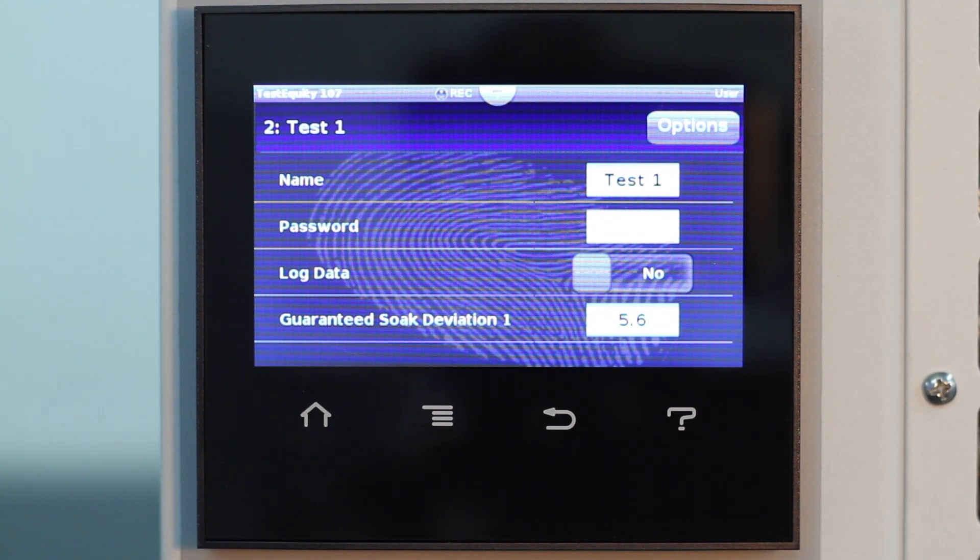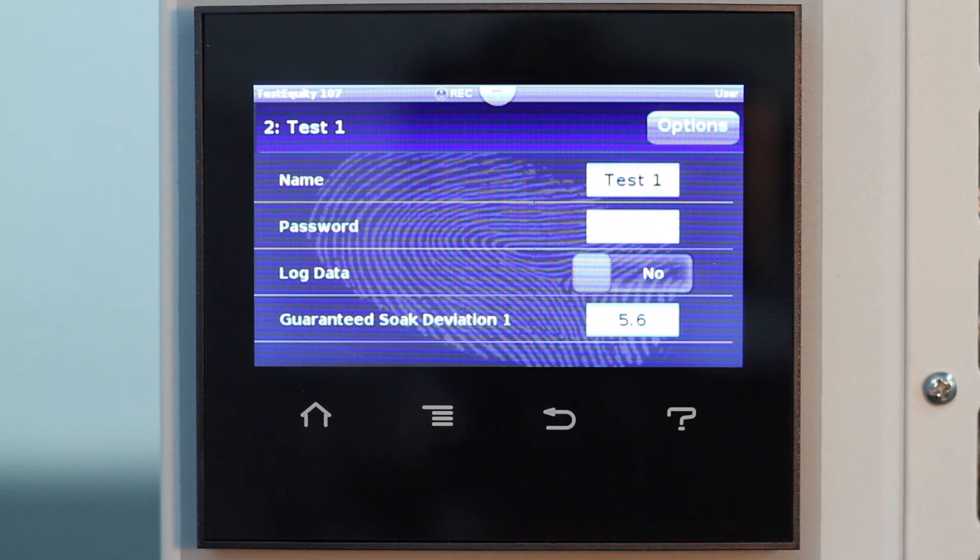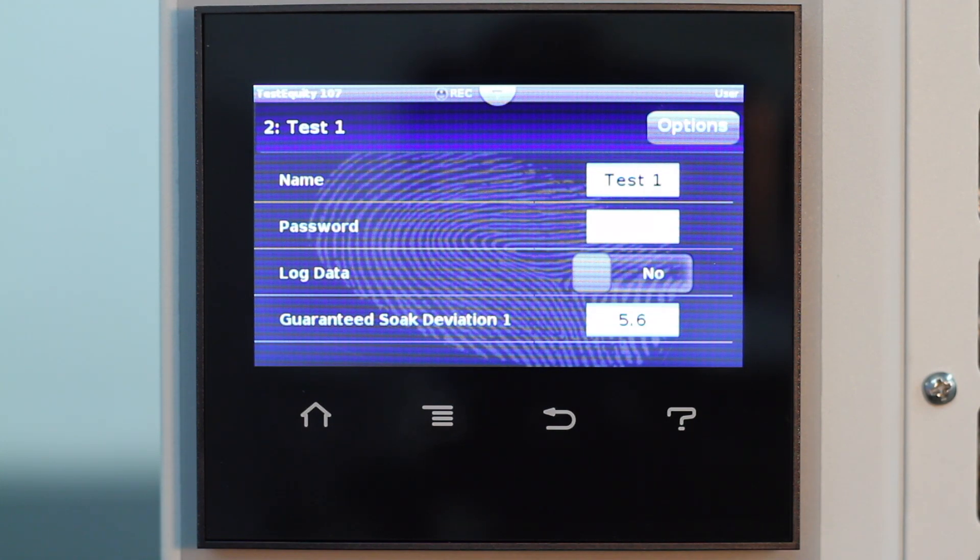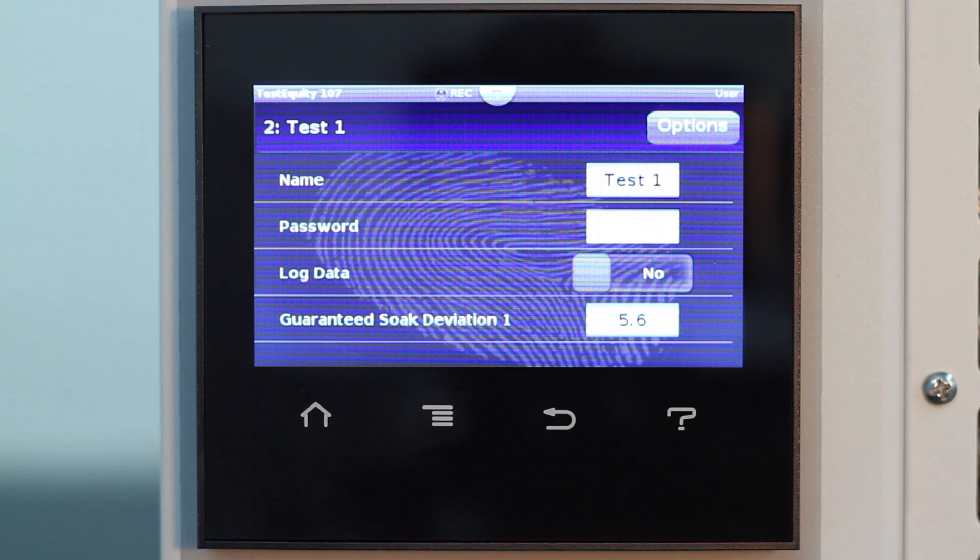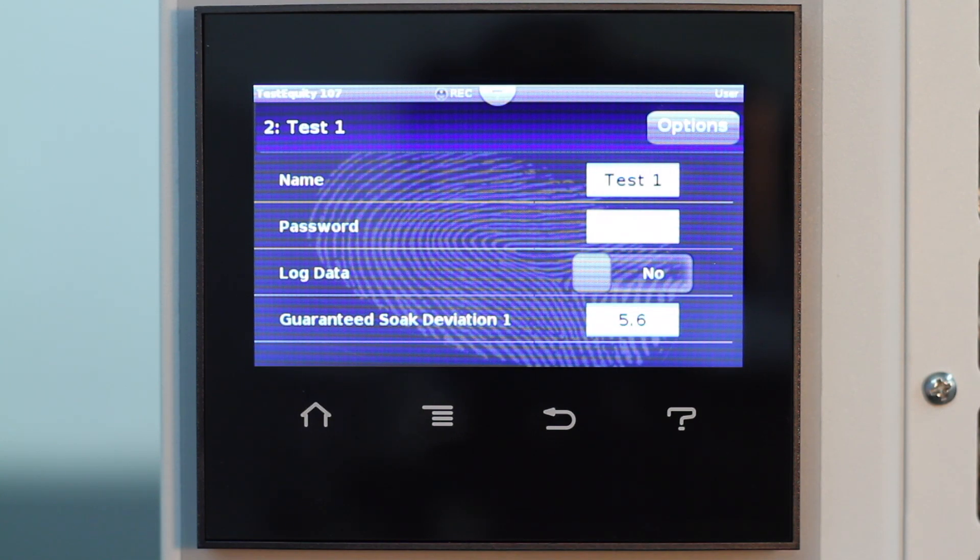You can also enter a guaranteed soak deviation value. If you have guaranteed soak enabled in a profile step, then the step will not advance in time until the chamber condition is within the guaranteed soak deviation value.